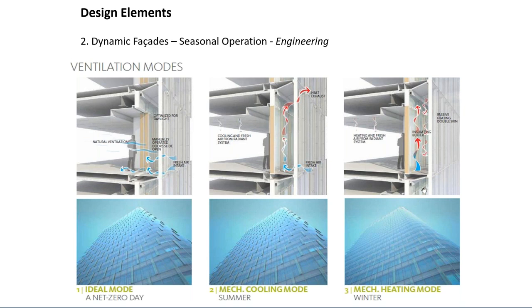And so there's a few different modes of operation, obviously. But in the mechanical cooling mode and in the mechanical heating mode, we're using passive chill beams. So there's no air to those, but you're basically using induction in the space to be able to condition the temperature in the space.